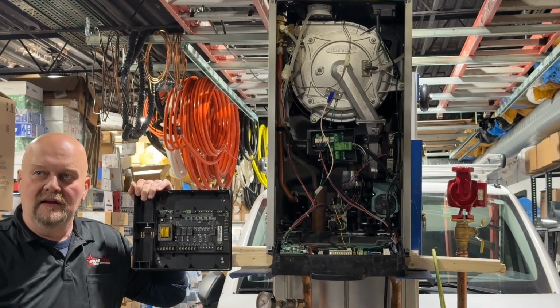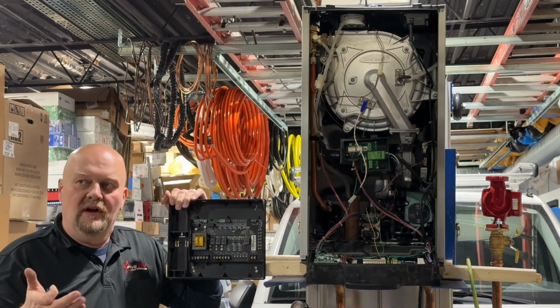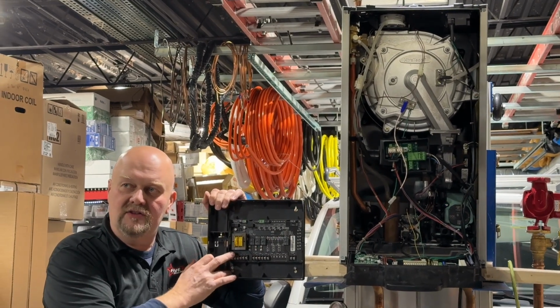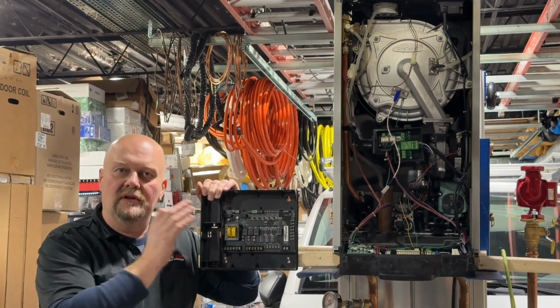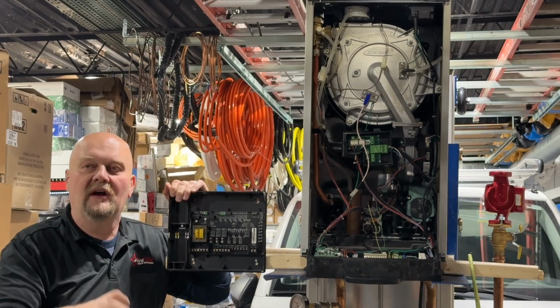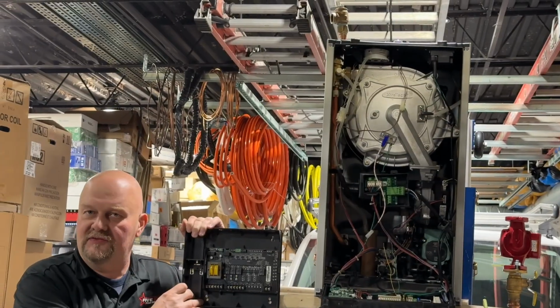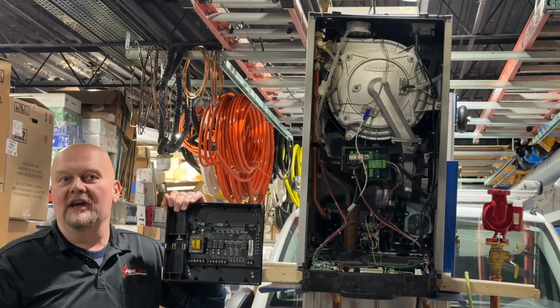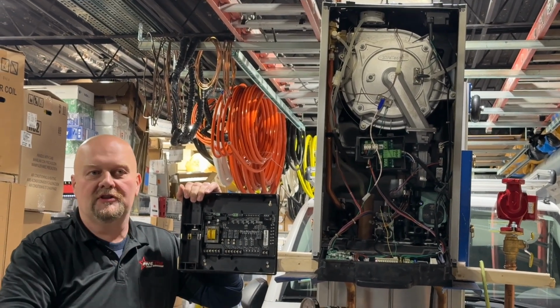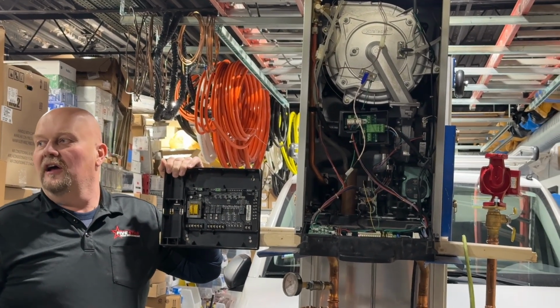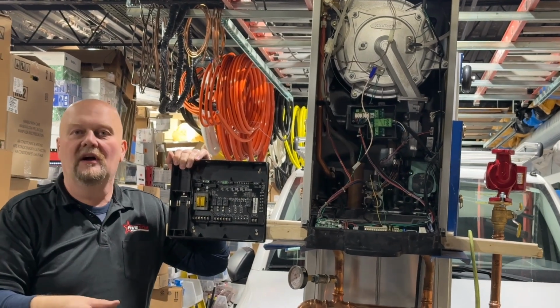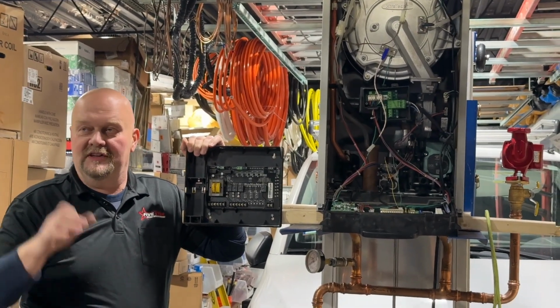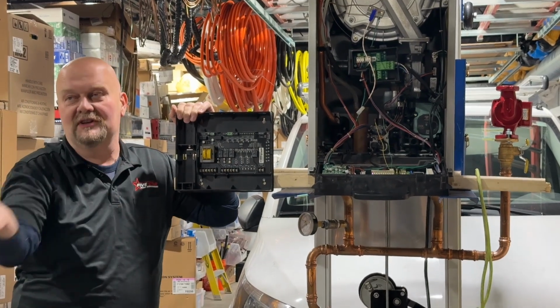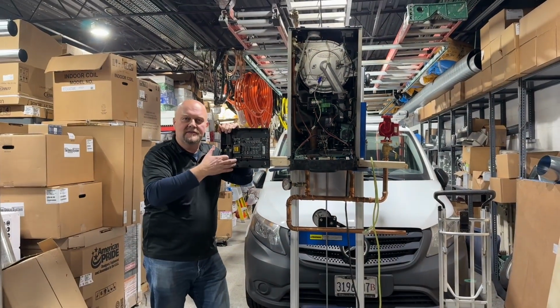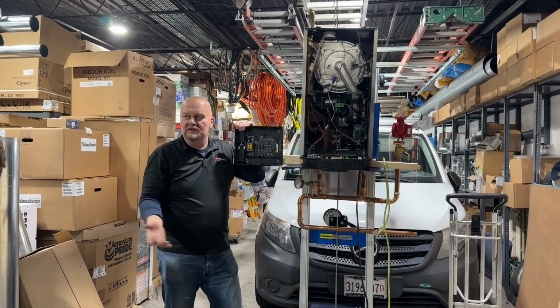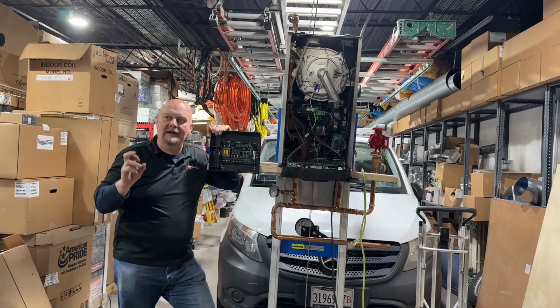Now we didn't do that, and the result was this. If this thinks you have it connected to a hot water tank, it will not turn on other pumps until your primary pump is satisfied, because it's thinking someone's taking a shower and you gotta make sure that you have hot water going to the storage tank, and you really don't care about heating someone's house until the hot water is satisfied. So that's a big problem if you're not using it in such a way, because then the other pumps do not get turned on. So if you have a control board like this, check for primary pump.